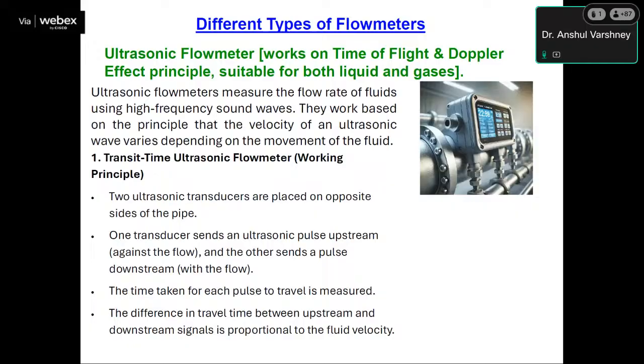So basically, ultrasonic flow meters measure the flow rate of fluids using high frequency sound waves. They work on the principle that the velocity of an ultrasonic wave varies depending upon the movement of the fluid. The working principle of the ultrasonic flow meter is transit time. Two ultrasonic transducers are placed on opposite sides of the pipe in which the fluid is flowing. One transducer sends an ultrasonic pulse upstream against the flow, and the other sends a pulse downstream with the flow. The time taken for each pulse to travel is measured. The difference in travel time between upstream and downstream signals is proportional to the fluid velocity.